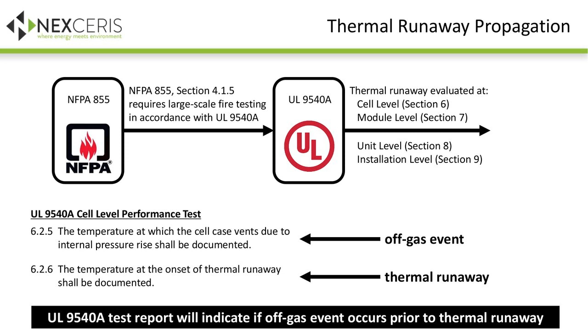When we look at those two discrete events, there's a point in time when the cell vent opens, and then a point in time at which it goes into thermal runaway. The differential between those two events creates an opportunity for fault detection, which is a unique way of looking at fault detection.